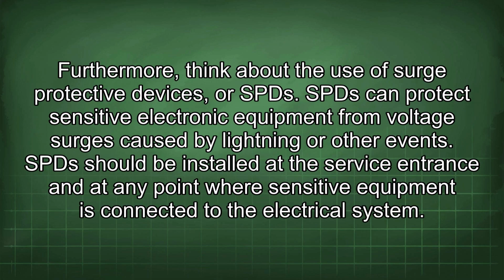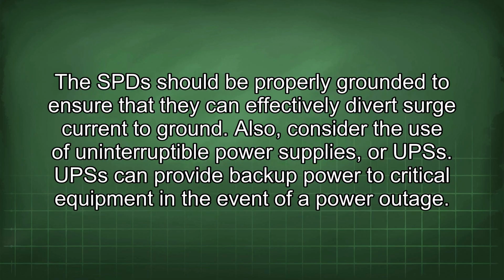Furthermore, think about the use of surge protective devices, or SPDs. SPDs can protect sensitive electronic equipment from voltage surges caused by lightning or other events. SPDs should be installed at the service entrance and at any point where sensitive equipment is connected to the electrical system. The SPDs should be properly grounded to ensure that they can effectively divert surge current to ground.